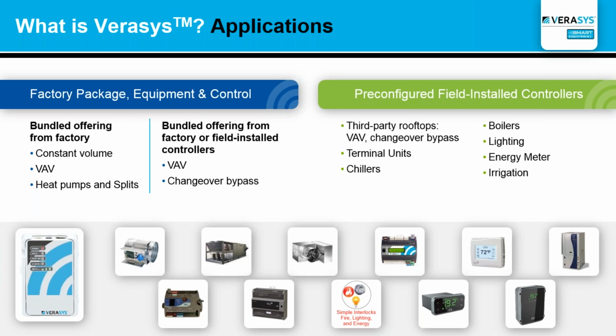The other applications we're providing take things to the next level with zoning systems. Even in 5,000 to 100,000 square foot buildings, you'll have situations requiring some level of zoning—changeover bypass systems, typical zone dampers with bypass dampers, or VAV systems using VAV boxes for zoning. At the same time, the equipment itself could change based on being a heat pump, constant volume, or splits. All of these applications are supported under Verasys with components available today, everything as a plug-and-play system with configurable controls.